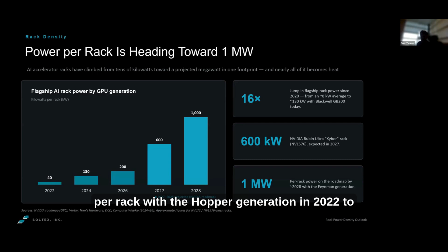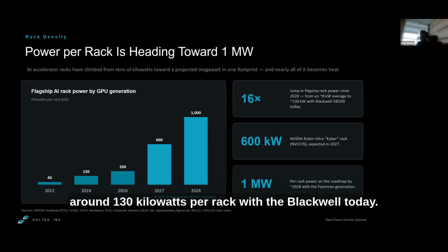This is what I mean by density. The chart depicts the power of a single AI rack across NVIDIA's GPU generations. We've gone from about 40 kilowatts per rack with the Hopper generation in 2022 to around 130 kilowatts per rack with Blackwell today. Next year's Rubin generation pushes towards 200 kilowatts per rack, and it really starts to take off past that point. Rubin Ultra is expected to near around 600 kilowatts in 2027, and the Feynman generation points towards a full megawatt per rack around 2028.